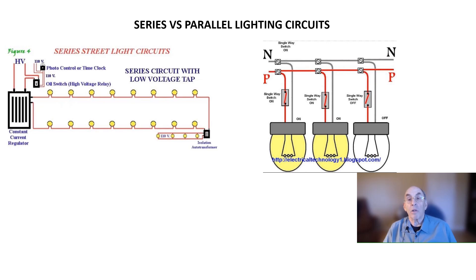One of the drawbacks of the parallel circuit is that the neutral and hot wires have some resistance. So the voltage across a lamp that is further from the transformer is less than across one that's closer to the transformer. This limits the number of lamps that can be put on the output of the transformer. This is less of a problem with LED lights that draw less current, but there still is a limitation on the number of lights that can be powered by a single transformer.